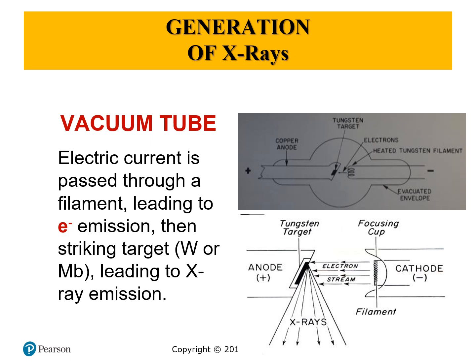Now remember when I told you to lower the current, you need to lower this current here. Lowering the current makes sure that your X-rays are just enough dose. If you have high current, that means high electron flow and very dense X-rays. Does it make sense? This should be in a vacuum tube. This is your heated tungsten filament.